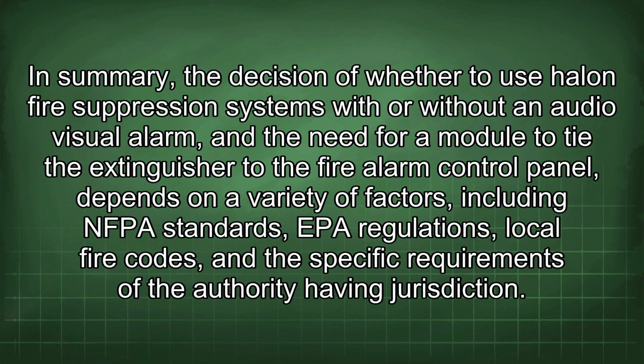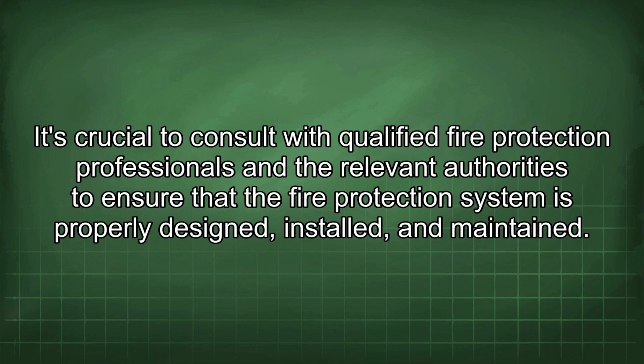In summary, the decision of whether to use Halon fire suppression systems with or without an audiovisual alarm, and the need for a module to tie the extinguisher to the fire alarm control panel, depends on a variety of factors, including NFPA standards, EPA regulations, local fire codes, and the specific requirements of the authority having jurisdiction. It's crucial to consult with qualified fire protection professionals and the relevant authorities to ensure that the fire protection system is properly designed, installed, and maintained.